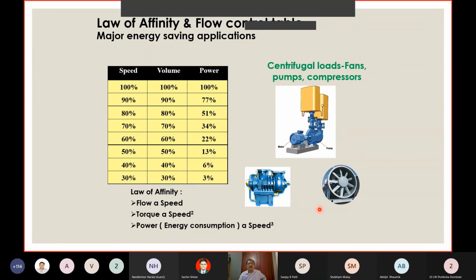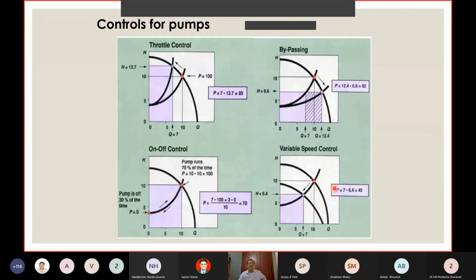We can see if there is a case study. Yes, there is one sample. When you use a throttle control like a valve, the energy saving available to you is only 11%. Whereas if you see variable speed control for the same, what is originally designed for 10 by 10 is reduced to, let's say, 7. Flow rate is reduced through the throttle to 7. When you throttle, the pressure will increase, it will not reduce. So the pressure has now gone up to 12.7 and the efficiency curve has shifted. Still you have a saving of 11%.